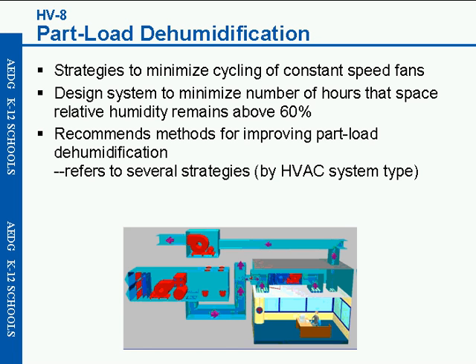Another important good design practice provided in the school's design guide is part load dehumidification. There are strategies provided to minimize cycling of constant speed fans. That is the primary concept here. The idea is to design a system to minimize the number of hours that space relative humidity remains above 60%. And there are recommended methods for improving the part load dehumidification for various HVAC system types.